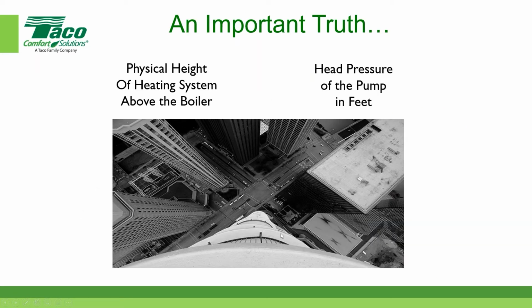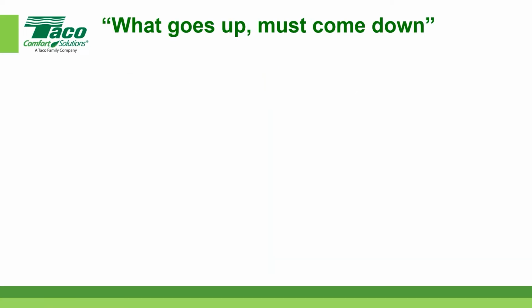Another thing about the hydraulics within the system links in the chain when I talked about air in the system. If I have a closed loop system, completely closed, and I've got all the air out of it, the circulator has no responsibility in lifting the fluid. We don't care, as far as the circulator sizing is concerned, how tall the house or the building is. Remember, what goes up must come down.